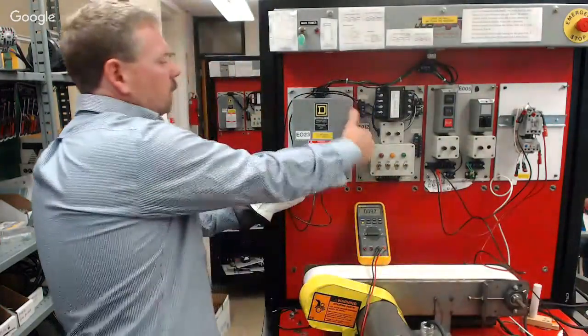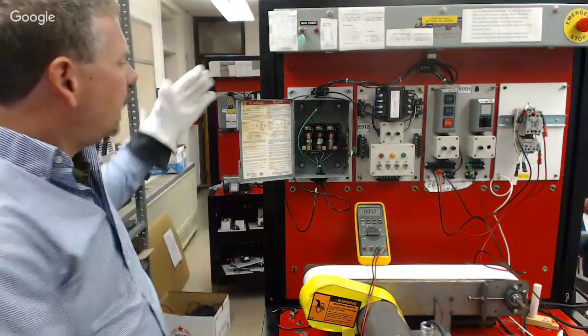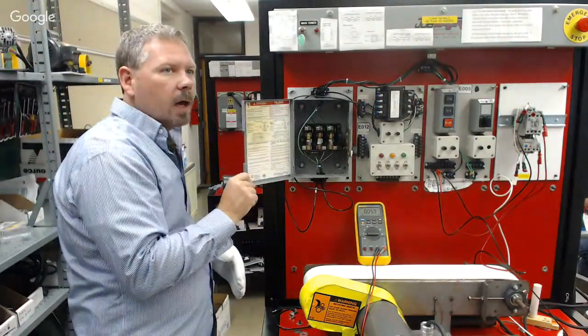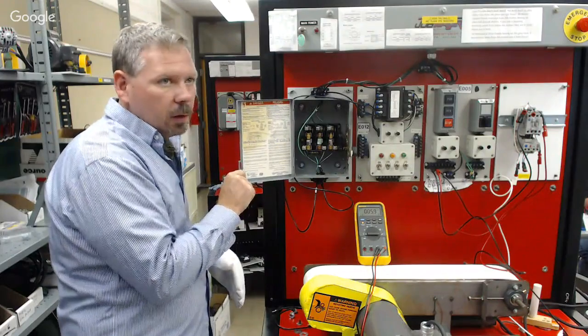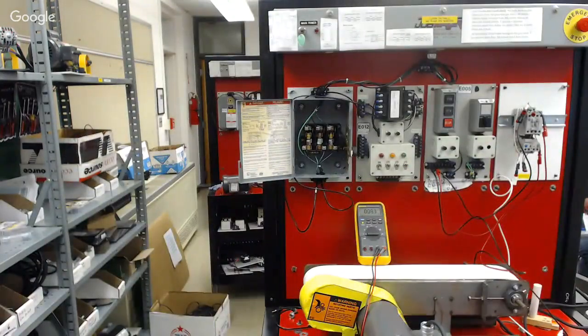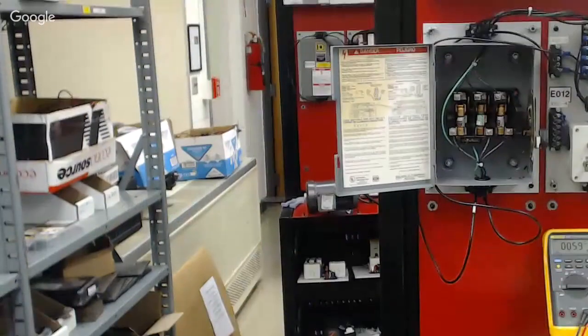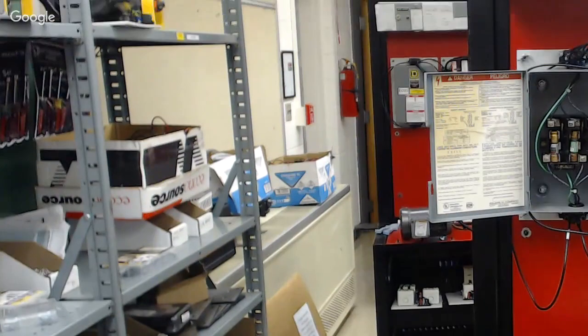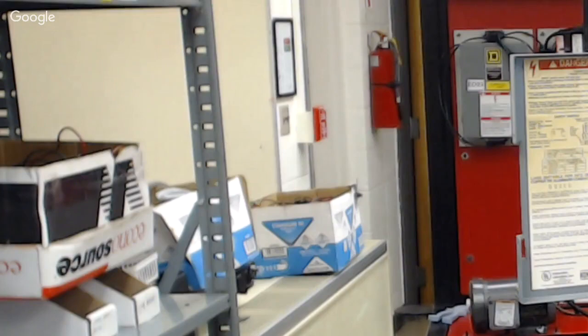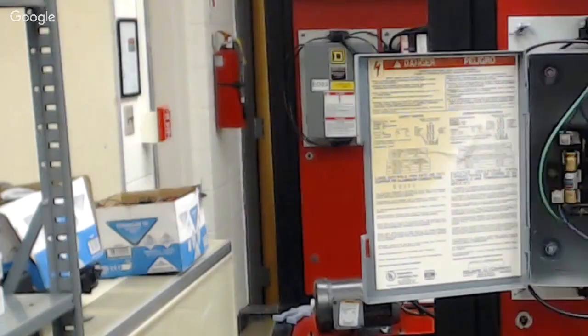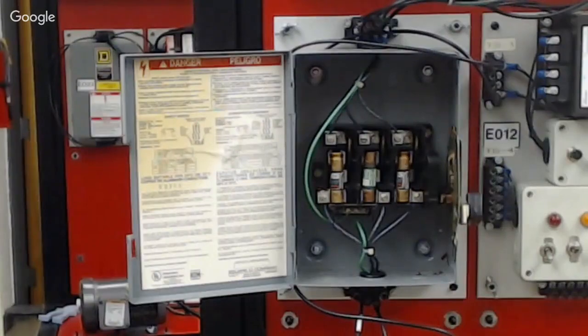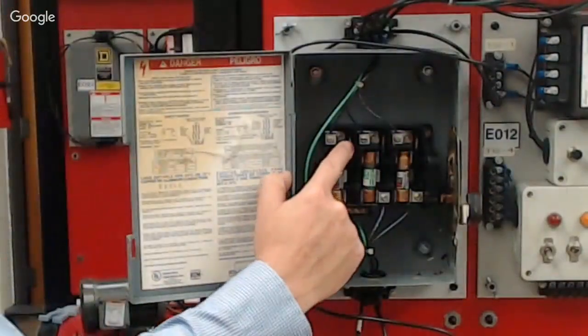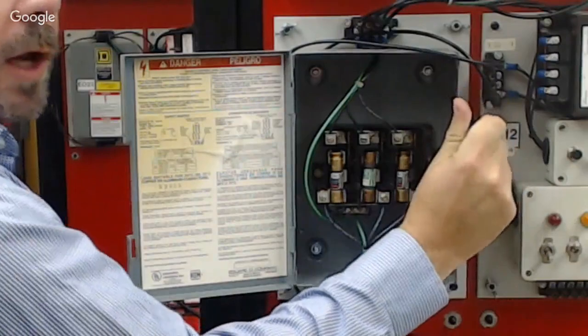If we look at this, we'll see that as this swings open, if we have an arc flash, which can happen, because if you look inside of this disconnect, you will see that there are small blades. And those blades, if they don't engage correctly, here, you'll watch the snap action. I think you can see the blades come in and out.